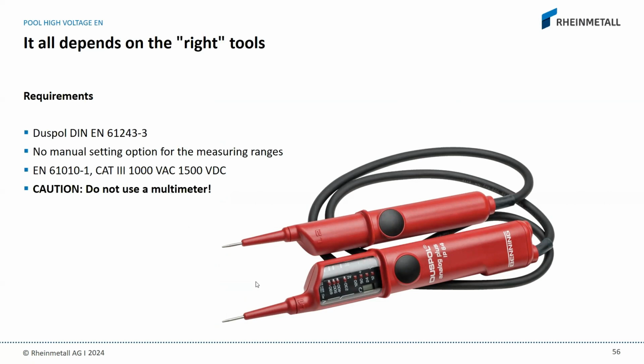We can use a multimeter as well, but we all know that if we're using a multimeter with a broken fuse inside, the display will always show 0, even if there is voltage on the system. Also, if we make a wrong adjustment on the multimeter's measurement setting, we get a 0. The correct reading we want to see on a voltage absence test should be 0.